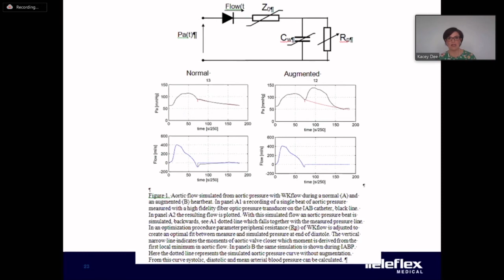Now, on the augmented beats, that top right graph, at the point of aortic valve opening, the pressure is estimated to match the normal or unassisted beat, and on the flow wave, the calibration from the normal beat is imposed at the end of systole. So the beat is then simulated backwards and, quote unquote, fit to the normal beat at the end of diastole. And this is done several times to optimize the fit. And based on these curves, the pressure values and volumes can then be calculated.